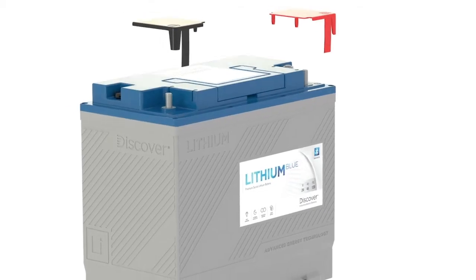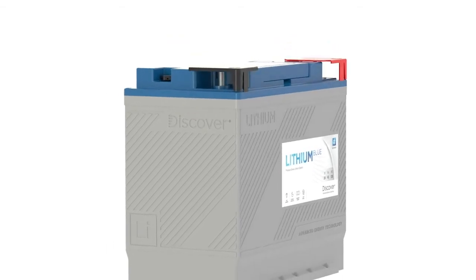That's a little different than the traditional approach. The advantage there is getting higher energy density in the same spot. And also you can parallel them up for the capacity, and you won't have the same issues of balancing between the batteries if you go all 36-volt batteries in parallel, rather than doing 12-volt in series to get there. Balancing is more complicated with single batteries in series versus one battery at nominal voltage. So there's an advantage to that, and lithium can do that. And we have batteries that are offered at that voltage.